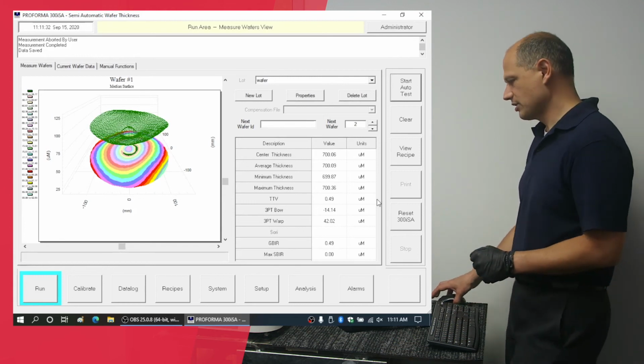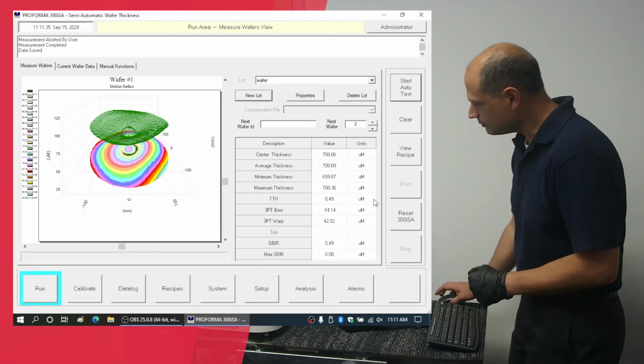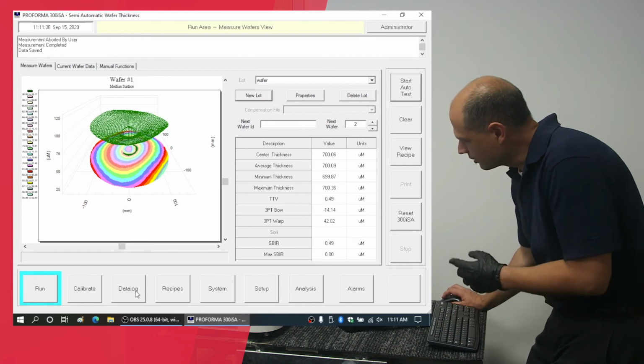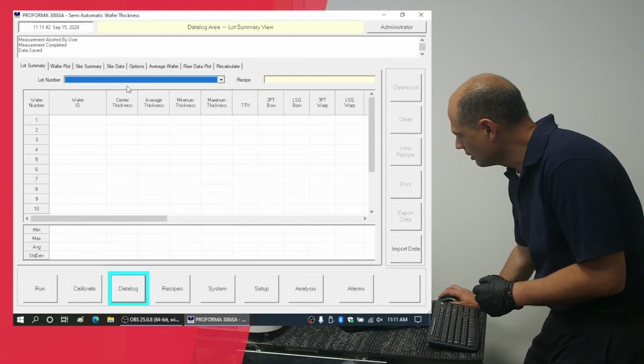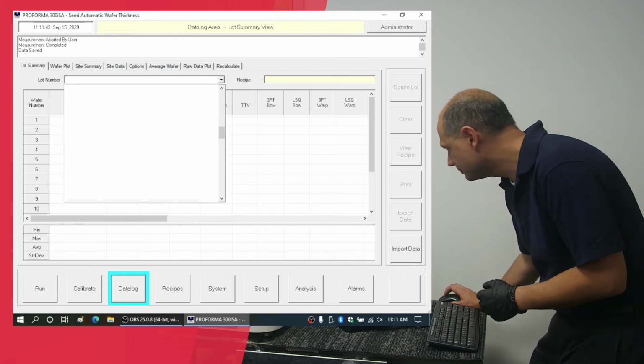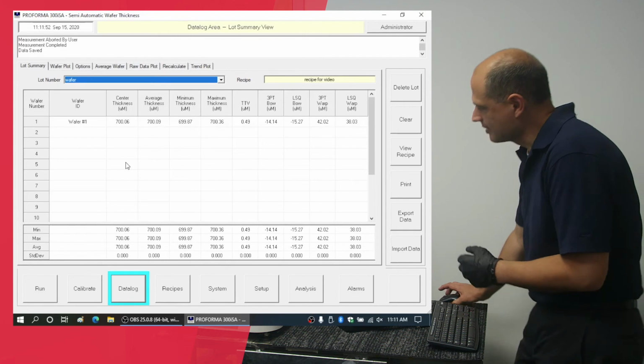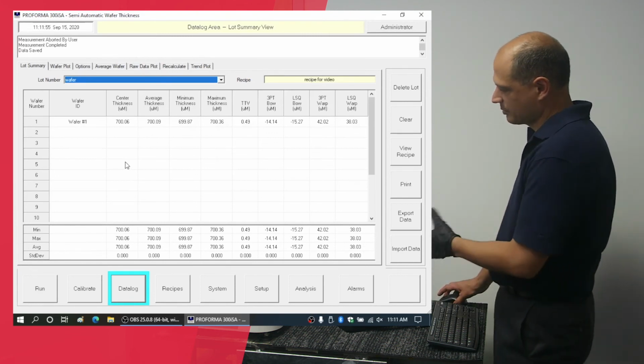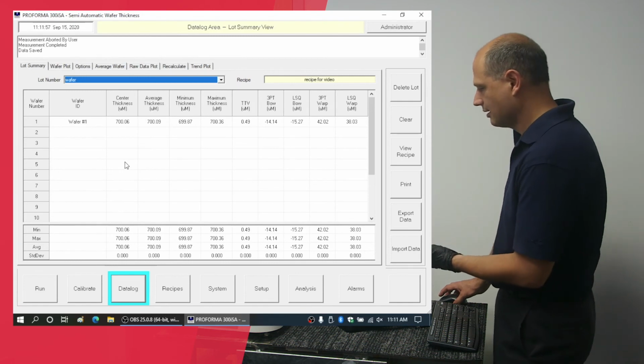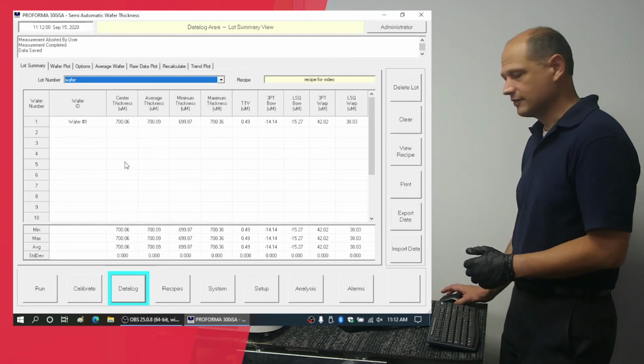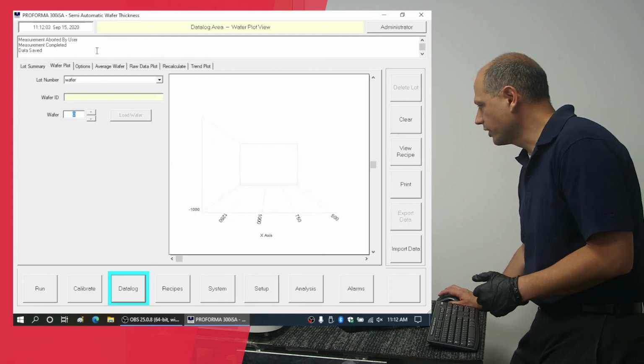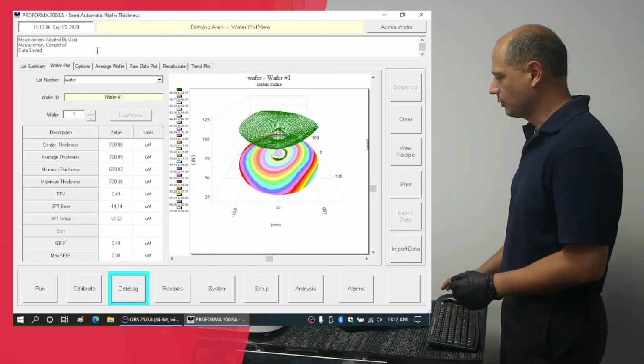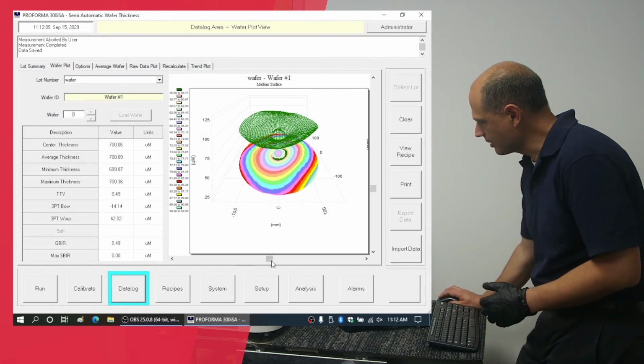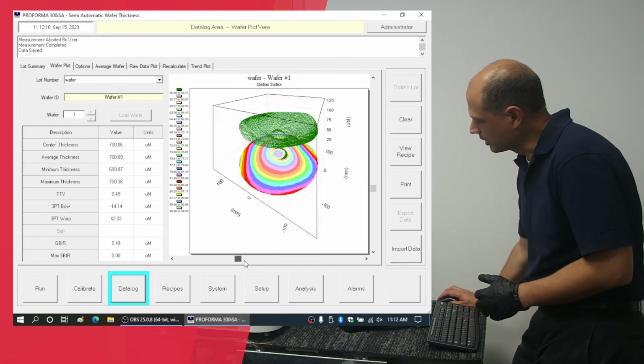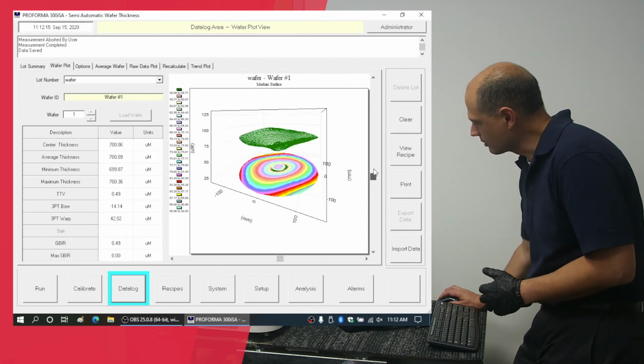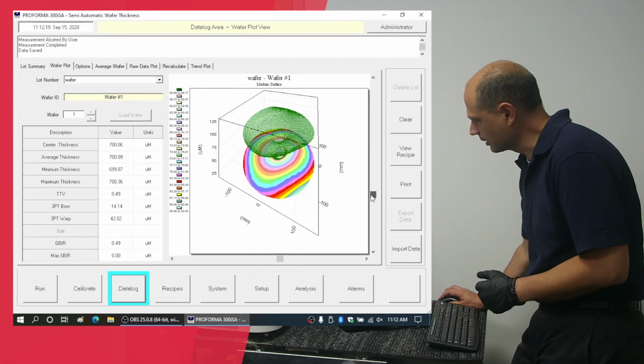The machine has now completed the measurements, and now we can see the results. If we go to the data log, we can select the measurement that we just ran, and we can see the data displayed in different ways. This is basically the raw data, the raw numbers, where we can see the minimums, maximums, averages, and standard deviations. But if we go to the Wafer Plot tab, then we can see a graphical representation of the data that we just gathered. We can move it around using our slide bars to have a better idea of what the wafer looks like.